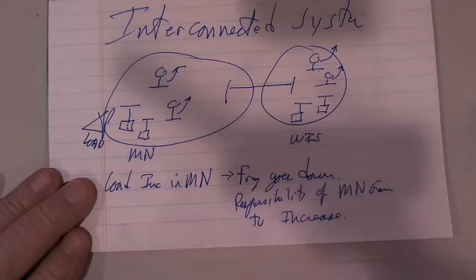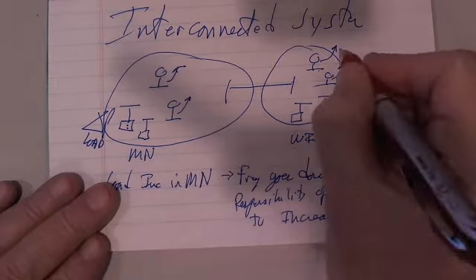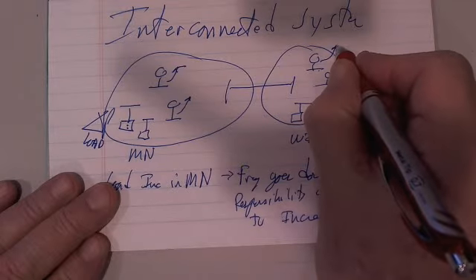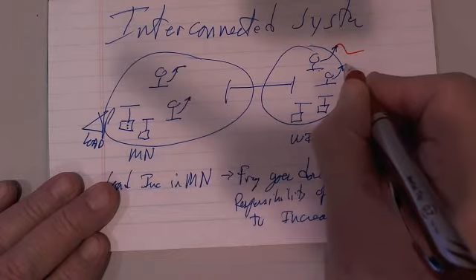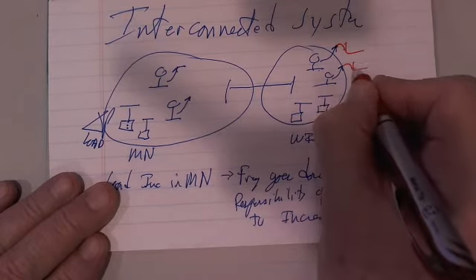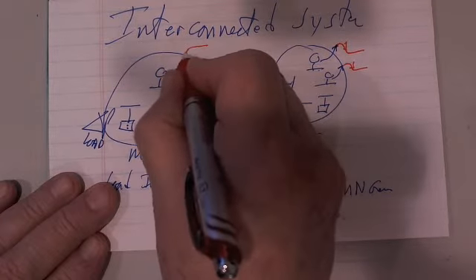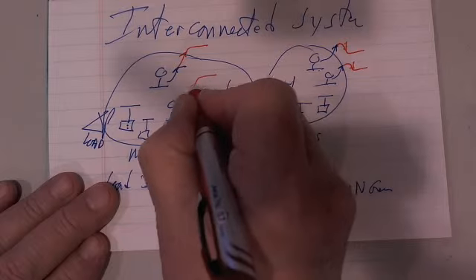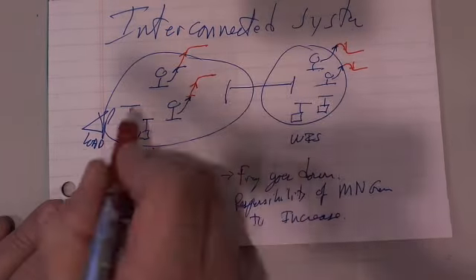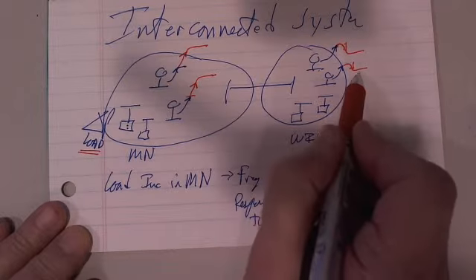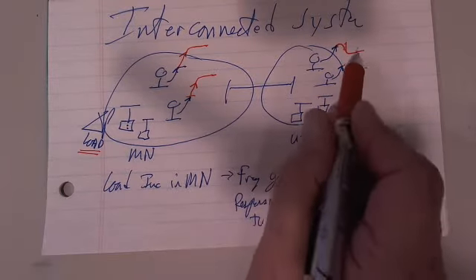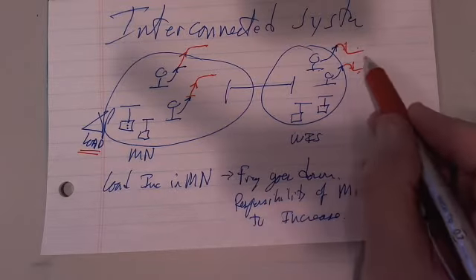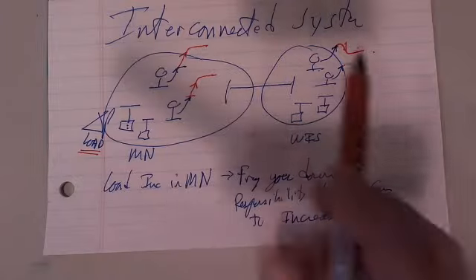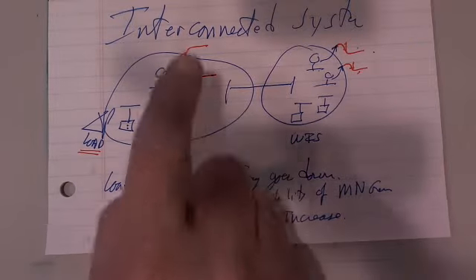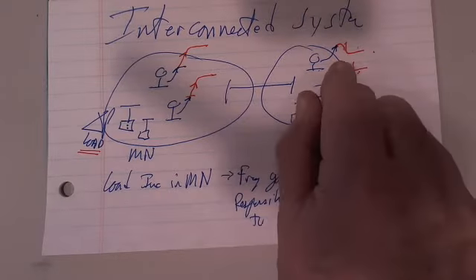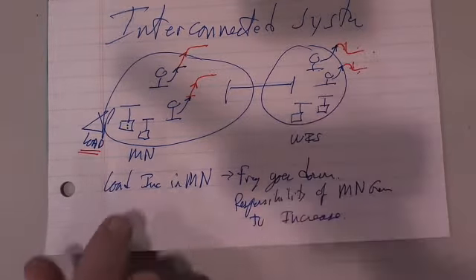Now, what should happen eventually, and that's where the AGC systems come in, is that this one says, your job is done, thank you very much, come back down. So now he's going to come back down, and these guys should keep going up until they level off, until the new level completely supplies the P load. These guys have gone back to their pre-event generator output. So these would go up and then back down, and these would go up and then continue up. These generators pick up the load increase, while these pick up a little while and then go back. But they all help with the frequency control.